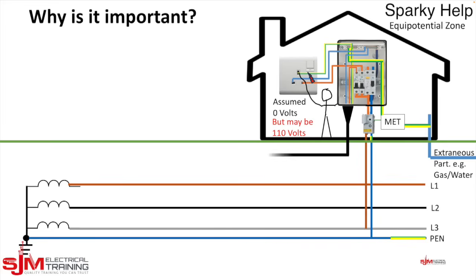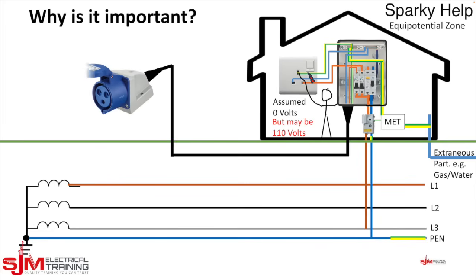So now what we'll do is take a supply outdoors, to whatever. It could be another building, it could be a socket, it could be an EV charger or anything else. So here we've taken the supply out, we've connected the line, the neutral and the CPC into the existing supply and fused it accordingly.